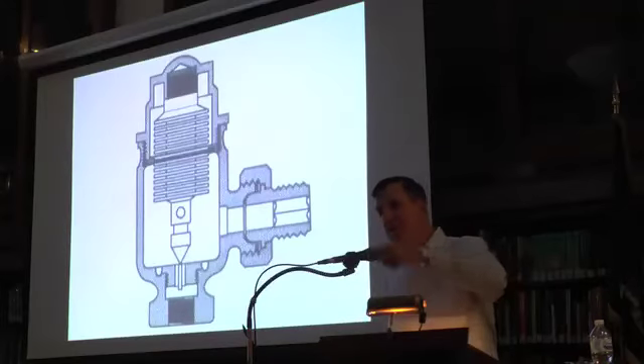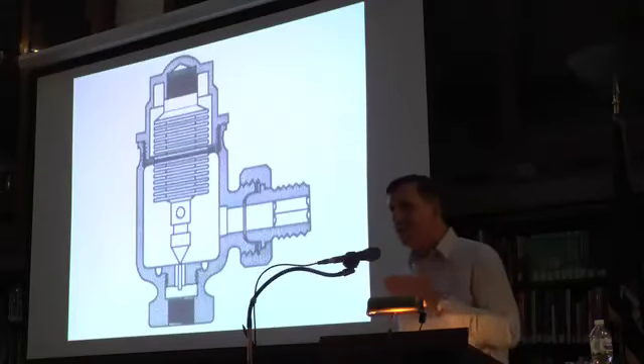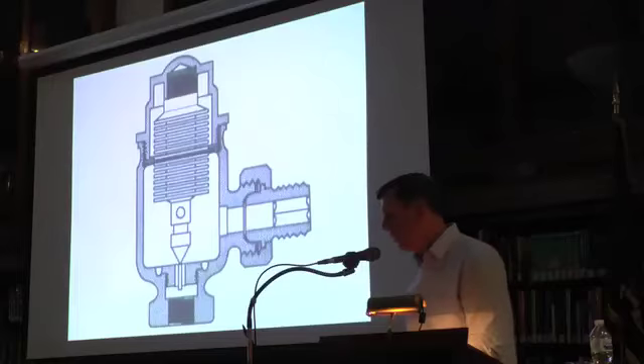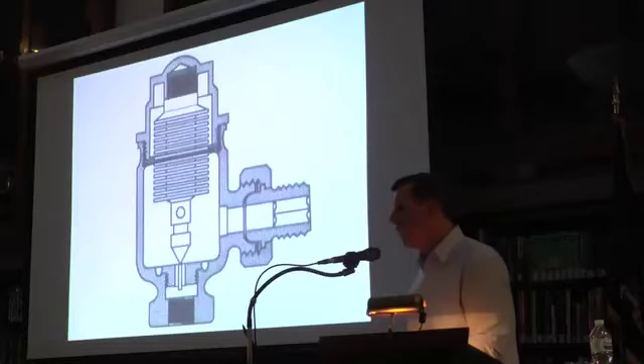You take a temperature across it. Those electronic things that have like a little laser pointer are cool. You check this side, check that side. You should see about a 10 degree drop in temperature from one side to the other. And those are typically line size to whatever size goes into the radiator and out of it.